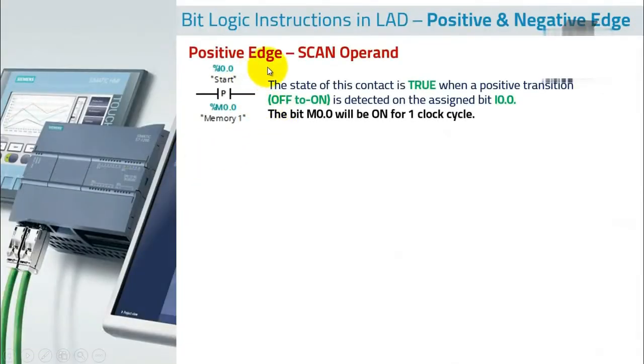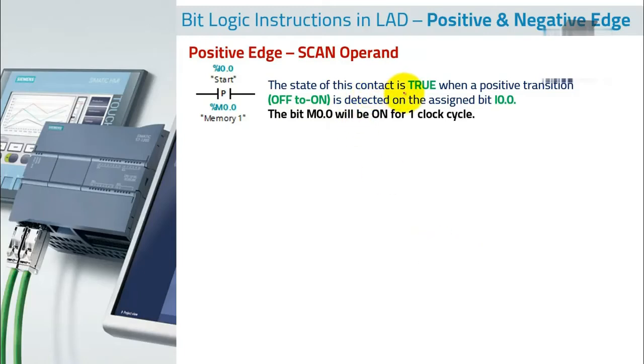Let's start with the positive edge scan operand. The symbol is similar to a NO contact but with a 'P' in the middle, indicating positive. The state of this contact is true when a positive transition — off to on — is detected on the assigned bit I0.0.